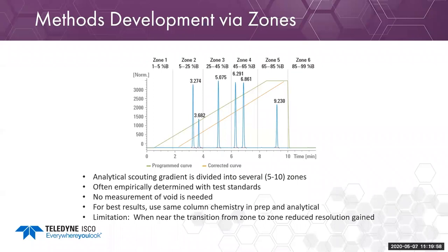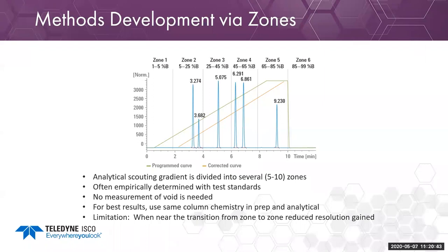This zone-based approach is usually calibrated in the lab by running your analytical system and correlating it to your prep system. Importantly, for this correlation to work you need to use the same column chemistry so that selectivity matches between prep and analytical. One limitation is that if you're at the edge of a zone, you start to lose optimal resolution and separating power.